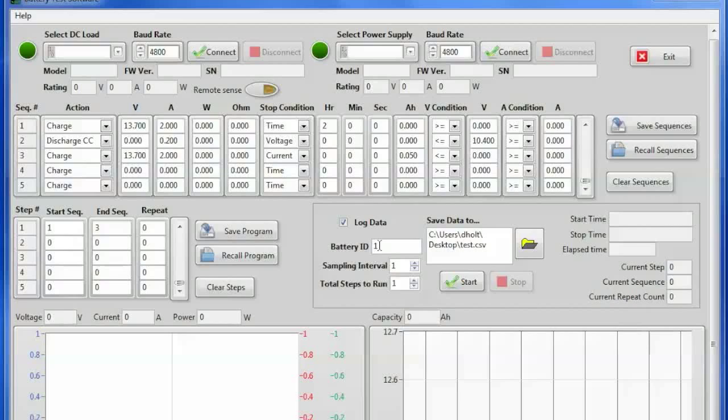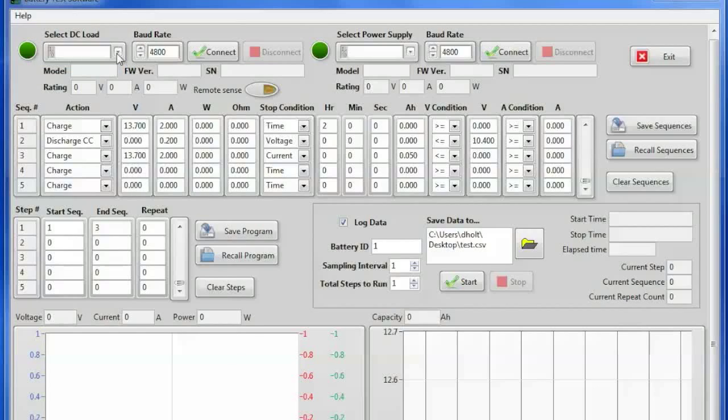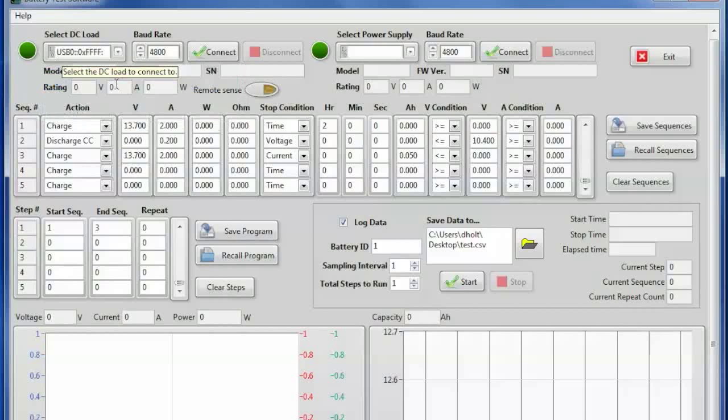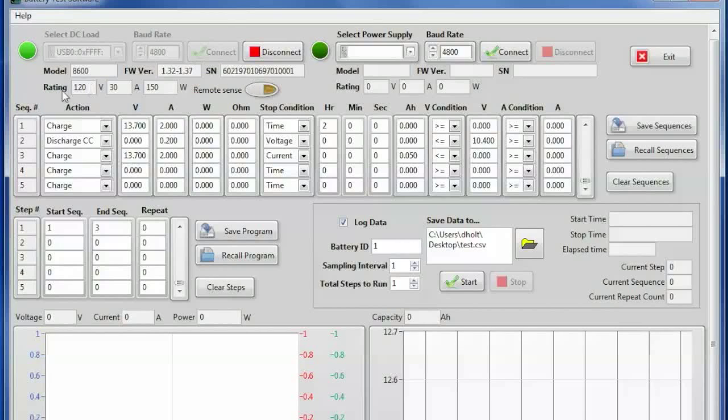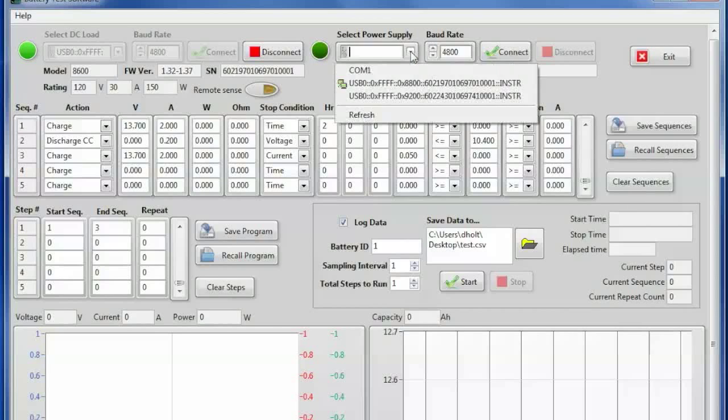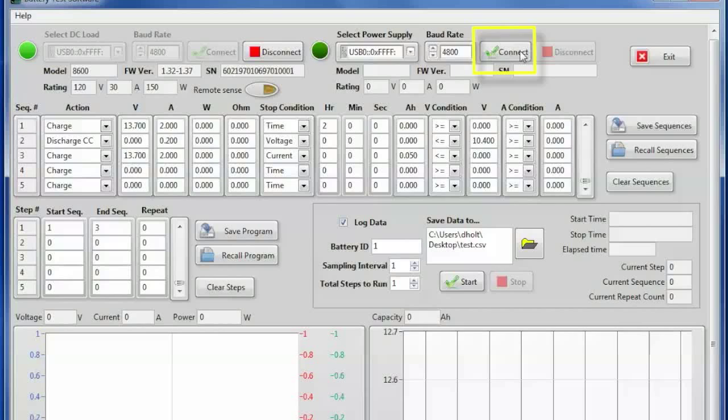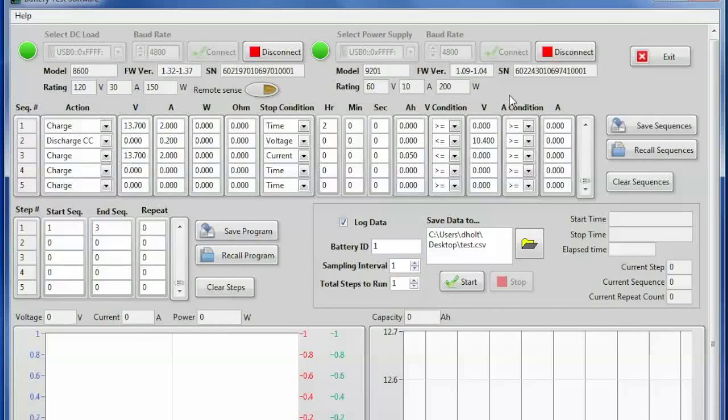Now that everything has been set up for this test now I need to connect my DC load. So I'll go up here and select and you'll see I found the 8600 and gave us a green light. Now I'm going to go over to the power supply and find the 9201. Now the load is connected. The power supply is connected. All of our parameters are entered.